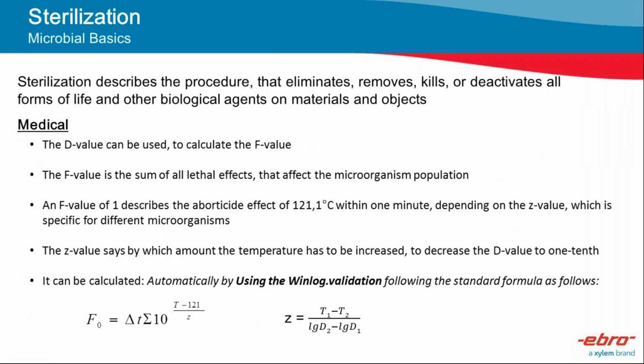Look at this slide. These are the requirements for validating a sterilization process in the medical and pharmaceutical application. The D value is very important. And the D value is a critical factor to arrive at the correct F value, F value being the sterilization value from the pharmaceutical perspective. And these things must be defined. And how are you able to arrive at the correct F value calculations in Ebro?